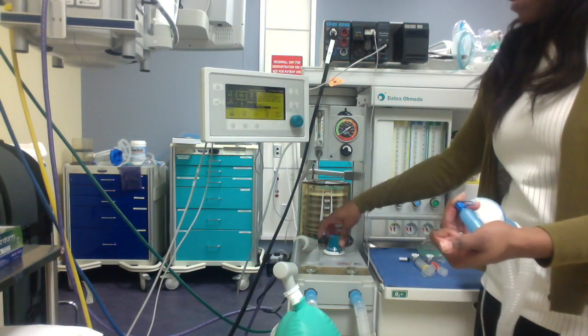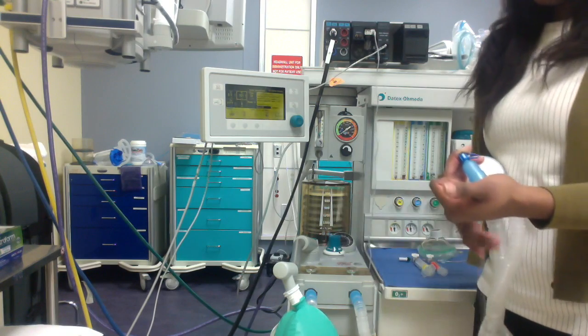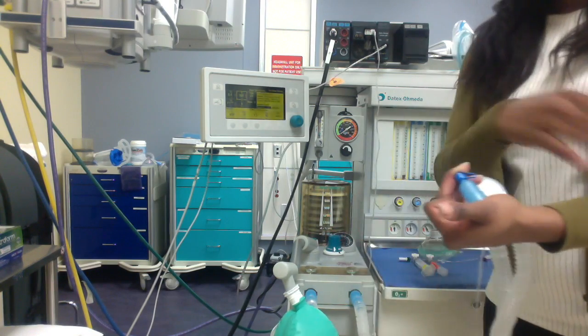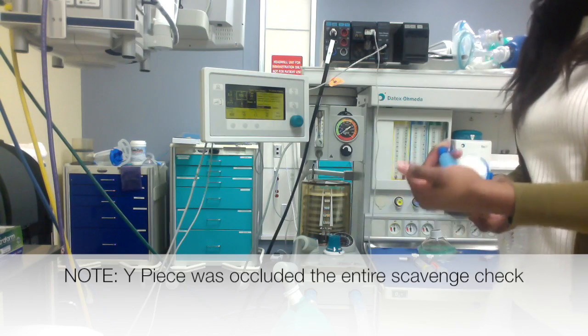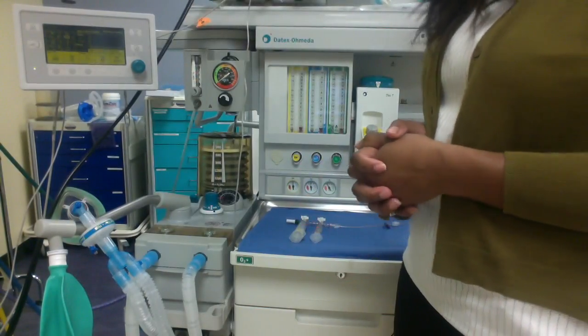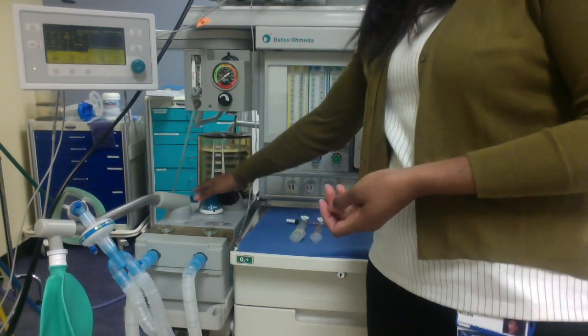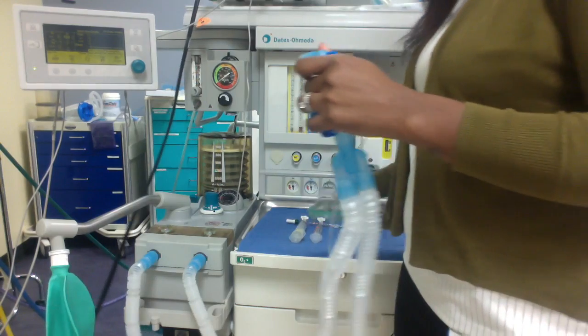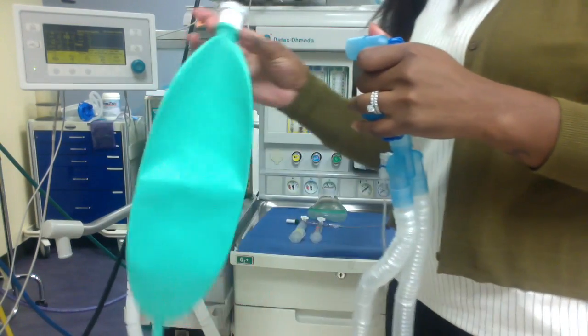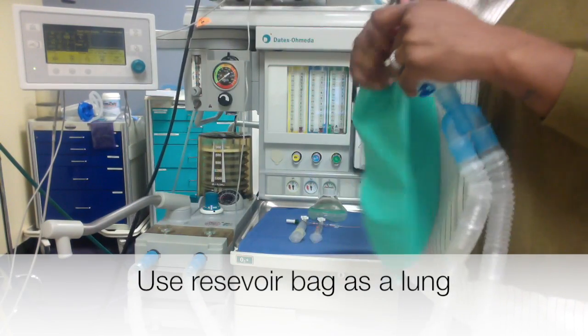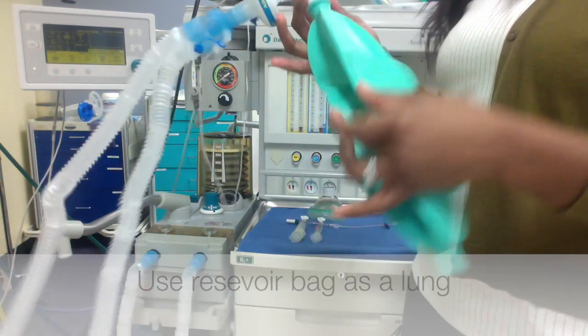And so then I would open my APL valve back up, and I do it this way so that I don't release a bunch of dust and particles into the air. So now we're done with that. Now that I've checked my scavenger system, I want to actually check my ventilator. So what I would do is I take this circuit, and I would take the mouthpiece off and use this bag, connect it to my Y piece, and use it as an artificial lung.